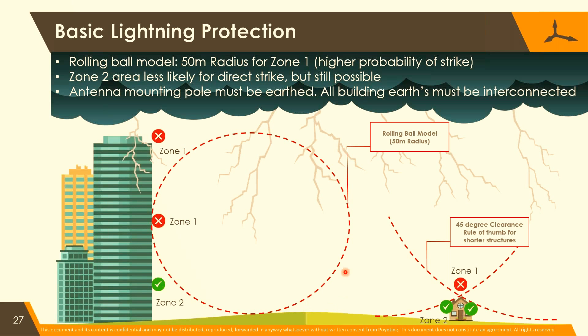If it's small, like a little tower, 20 or 30 meters high, you can see no problem. But this is the rolling ball model — it's a very good guideline in terms of where things can be hit by lightning. Do not believe that on certain high structures, mounting away from the top will protect you against lightning. The rolling ball is the most accurate way of doing it.